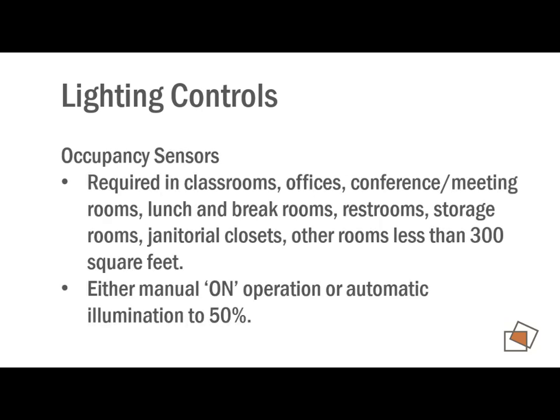And a thing to note is where you have these occupancy sensors applied, you have to have an on operation. So you have to push the button to turn the lights on. Or if it automatically turns on, they can only turn on to 50%, and then you push the button and they come all the way up to full brightness. They're trying to eliminate unnecessary turning on of light fixtures as much as the automatic turn off. I think occupancy sensors are a net win, but we probably end up turning our lights on in some cases when we might not have. So they're saying now that if you're going to put an occupancy sensor in, you have to push the button and make the lights come on.